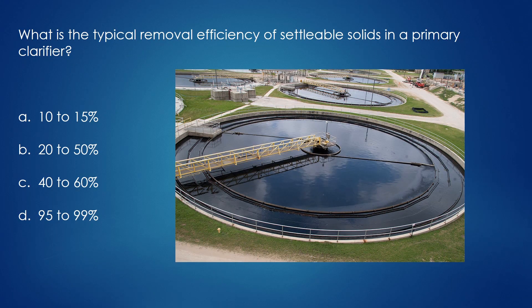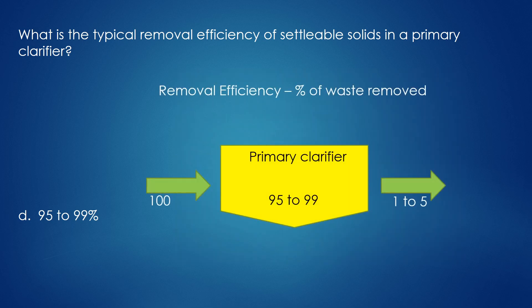What is the typical removal efficiency of settleable solids in a primary clarifier? 95-99%. Removal efficiency is the percentage of waste removed from the wastewater. For example, if 100 settleable solids entered the primary clarifier, 95-99 of them settled to the bottom and were removed. Only 1-5 settleable solids left the primary clarifier in the effluent.